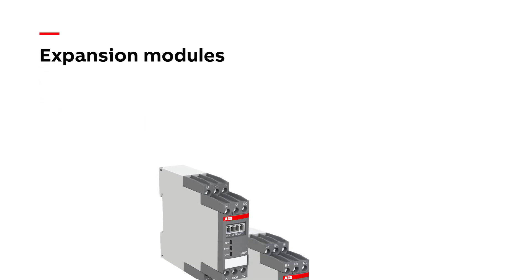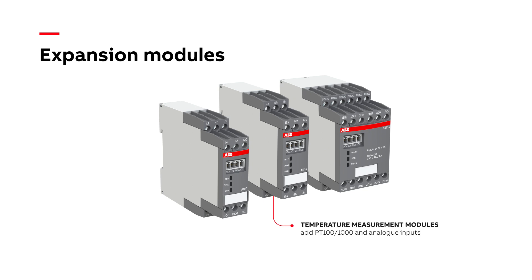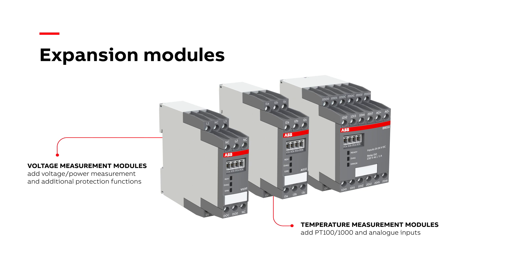Experience flexibility with a variety of expansion modules. Temperature measurement modules add PT100, PT1000, and analog inputs. Voltage measurement modules add voltage or power measurement and additional protection functions. IO modules add 8 DIs, 4 DOs, and 1 AO.